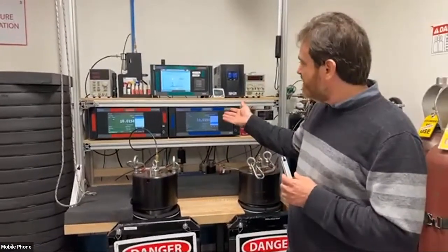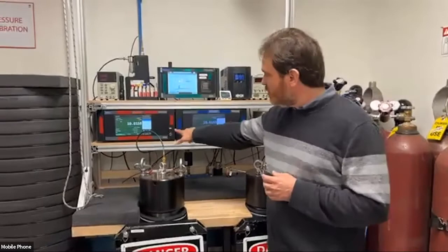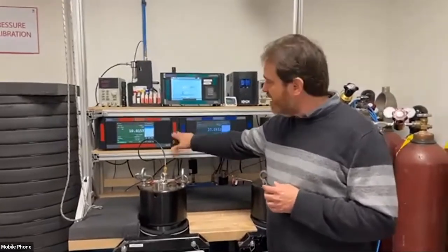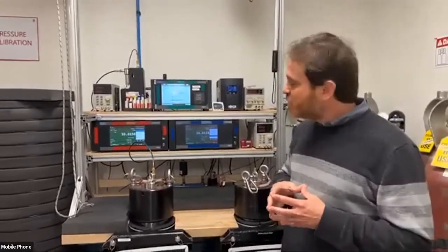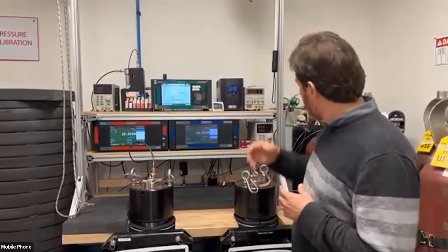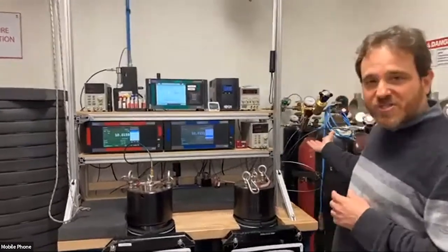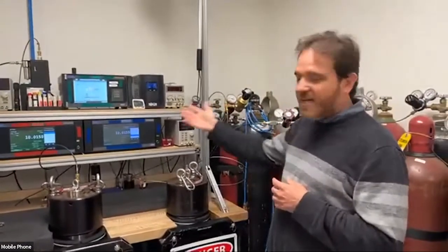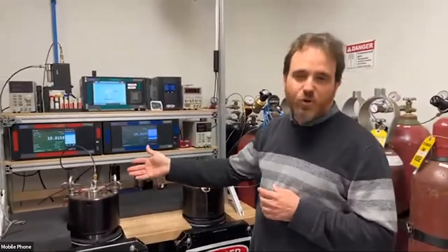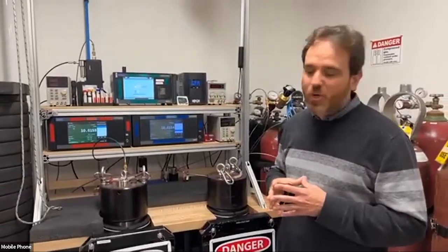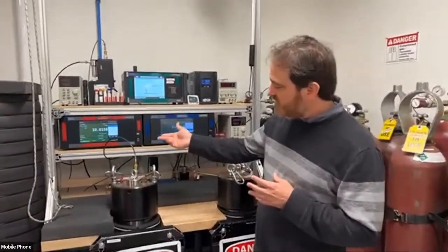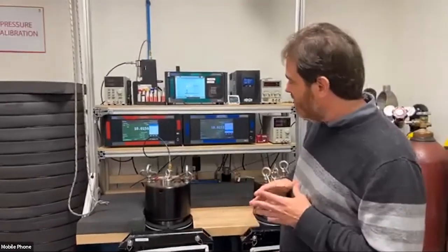So right now we typically use these two pressure controllers that are located here at the bottom. These are Mensor CPC 6000 pressure controllers. And we have nitrogen cylinder gas, which is utilized by the pressure controllers in order to pressurize the vessels at the different plateau points. We can actually see that one tank is running right now.